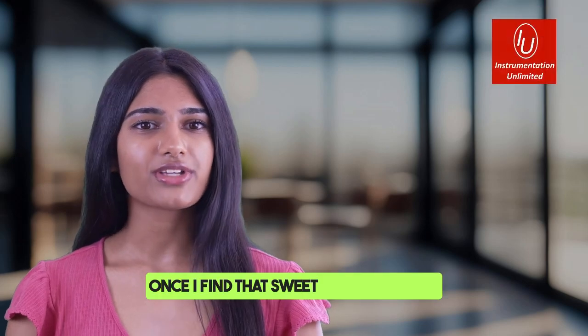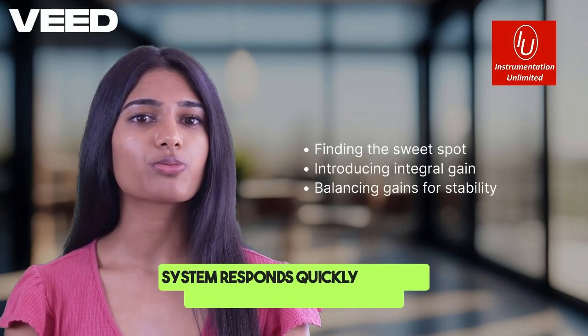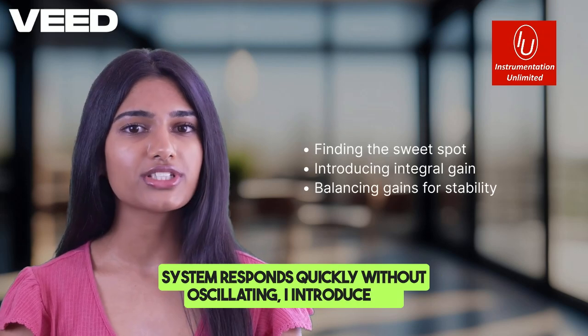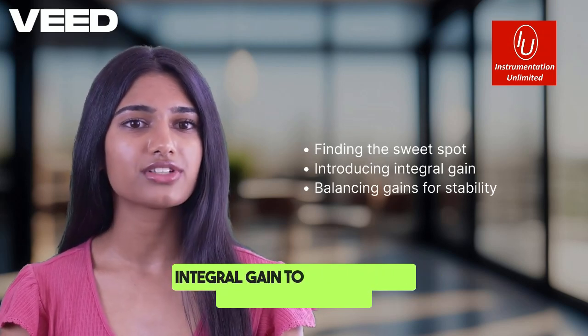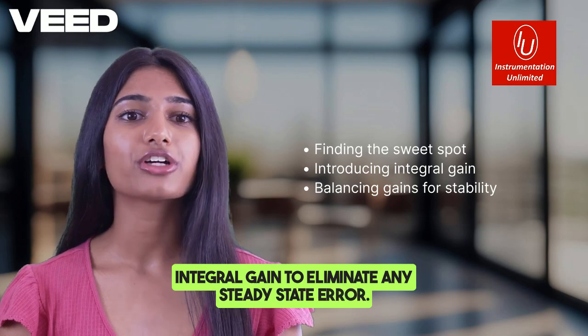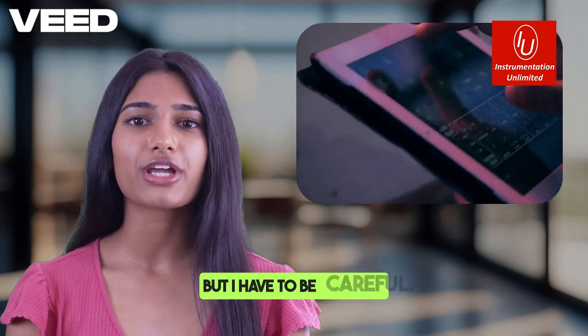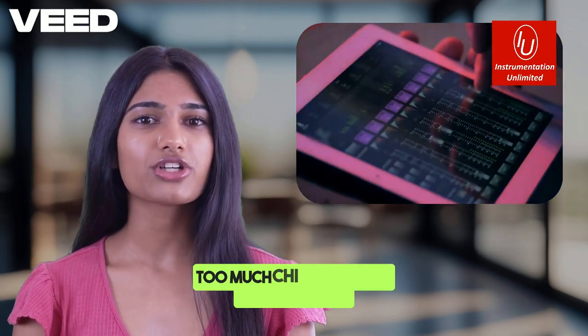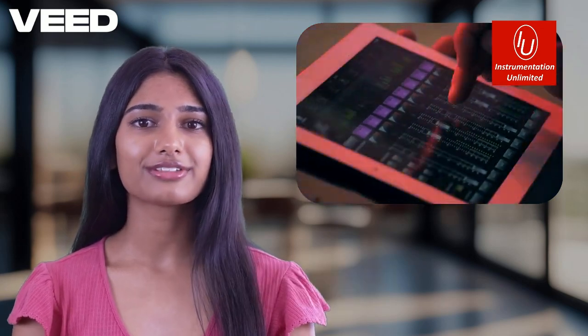Once I find that sweet spot where the system responds quickly without oscillating, I introduce the integral gain, Ki, to eliminate any steady-state error. But I have to be careful. Too much Ki can lead to overshooting.